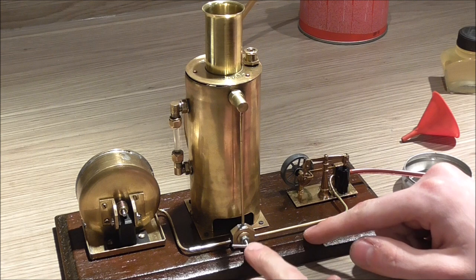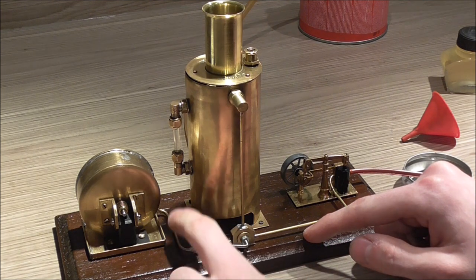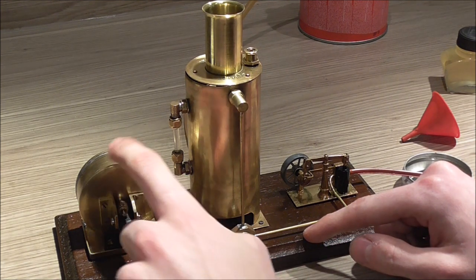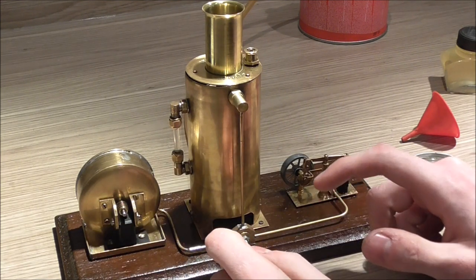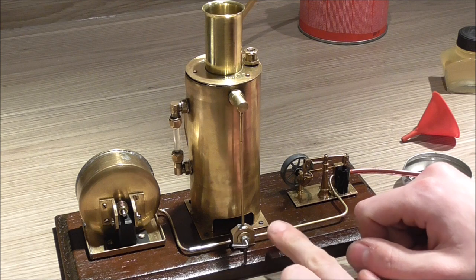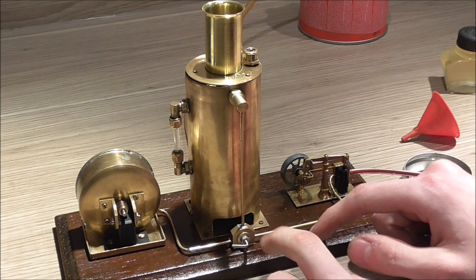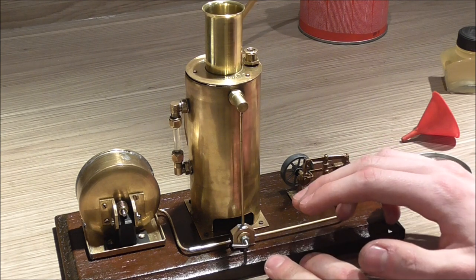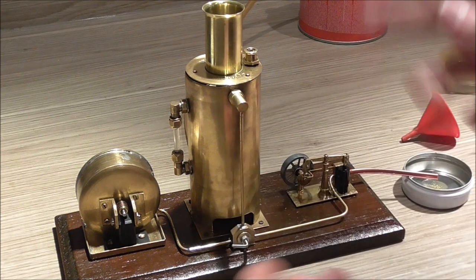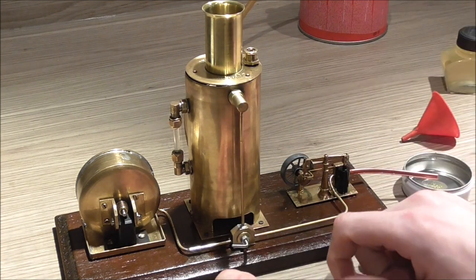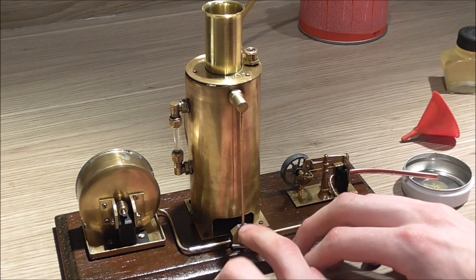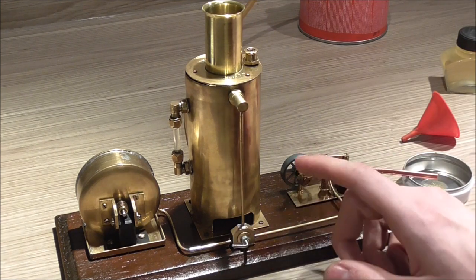I've currently set the lever here to the left so that any steam is going to evaporate into the turbine. And we know that we're steamed up. The second concern I have is that this valve may be leaking quite badly. I noticed there was some kind of hissing noise which I'm not sure, either it was, you know, the hose from the compressor into the boiler or it was the valve.